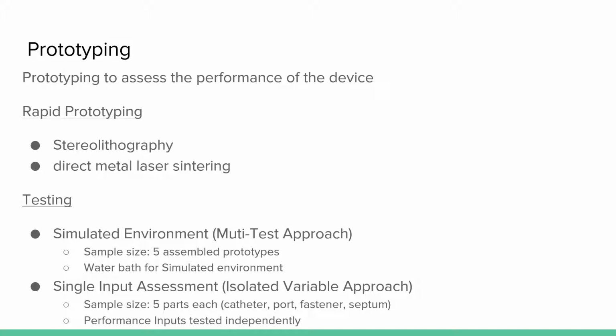So for our rapid prototyping, we will mainly be testing the performance of the device. We chose to use stereolithography to fabricate the plastic parts out of liquid resin and direct metal laser sintering for our titanium base. We considered 2 prototyping approaches for our testing. The first was a multi-test approach in which we tested 5 assembled prototypes in a water bath simulating an in vivo environment. The device can be subjected to forces and temperatures similar to what would be found in the body.